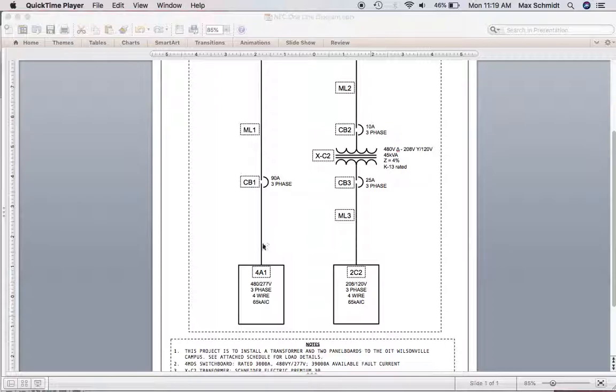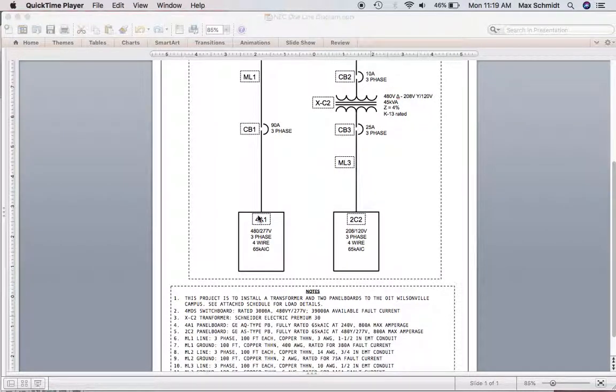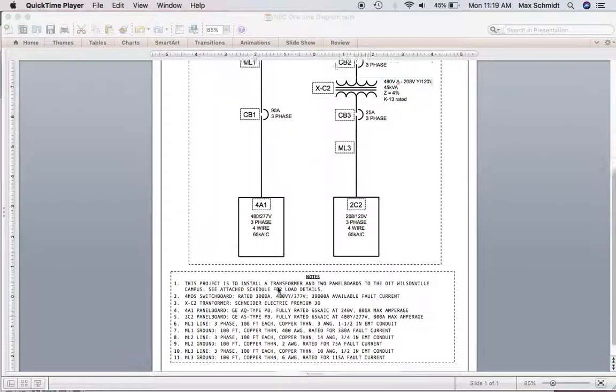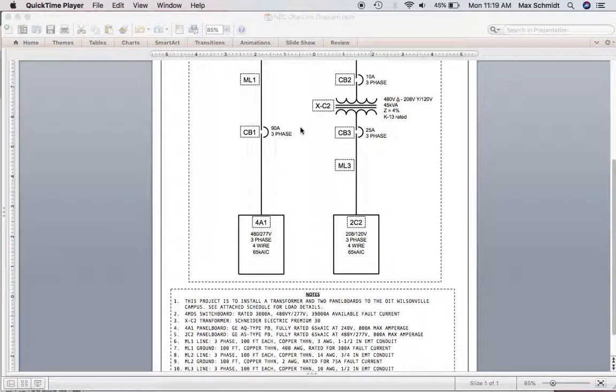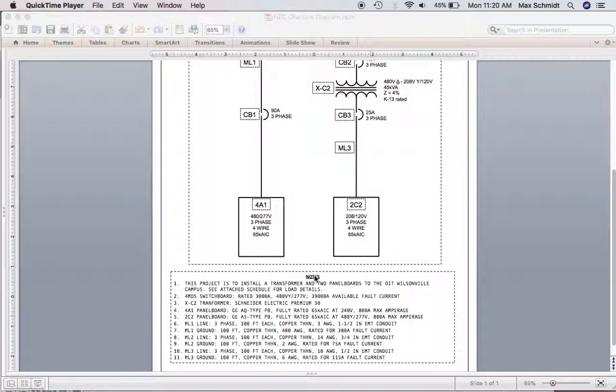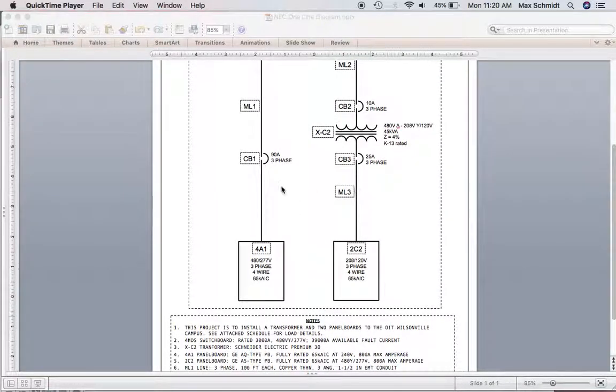So for that, I took the phase current coming out of here for each line, multiplied it by 1.25, and then sized up on the NEC sheet to get those gauge ratings. And then for the circuit breaker sizing, I didn't multiply by 1.25 for my phase current coming out here, and then I sized that down for NEC. So I did that for all 3 lines and then for all 3 circuit breakers. So yeah, the circuit breaker ratings are all provided in the one-line diagram.